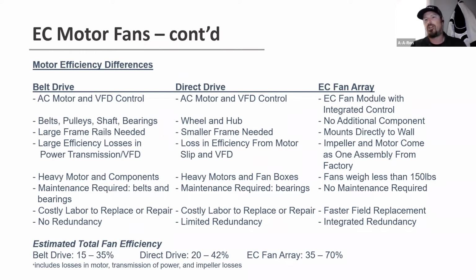And the biggest component is weight. The heaviest fan that we even supply is about 150 pounds. And then you look at some of these 5, 10, 15 horsepower motors weigh anywhere from 200 to 600 pounds, requiring gantry systems and a lot of labor costs to replace those. We don't have any maintenance. They're strictly plug and play, no bearings to grease, no belt to change. If a fan were to fail, you just remove it from the system, throw it away, and then put a new one on. And then we add integrated redundancy. In most cases, all of our systems tend to be about N+1. That way, if a fan does fail, the customer doesn't see any interruption in their airflow.